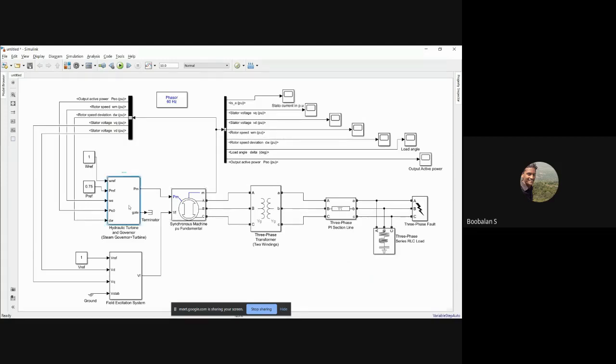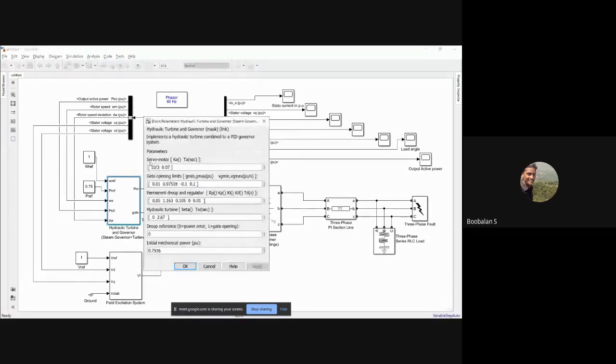So you could see here there is a servo motor. The servo motor is going to adjust my fluid, right? With the help of the servo motor only, the hydraulic piston is going to be actuated. Based upon that, my control valve is going to be moving, and based upon this control valve moving only, you are able to control the steam flow in our pipeline, and able to measure these things, right?